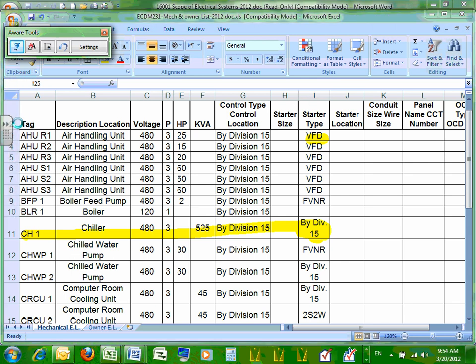Well, I'm going to be a little careful. Because of the manufacturing and because of the higher watt density in that computer room, I think we're going to need a chiller all year round. Sometimes that can be non-coincidental, I don't think. So the chiller's going to probably be an annual year-round load, and you know, the boiler. In reality, they're going to have processes that need high hot water for their manufacturing and process load. So the boiler's probably year-round, which is again another one that you might have thought was non-coincidental.